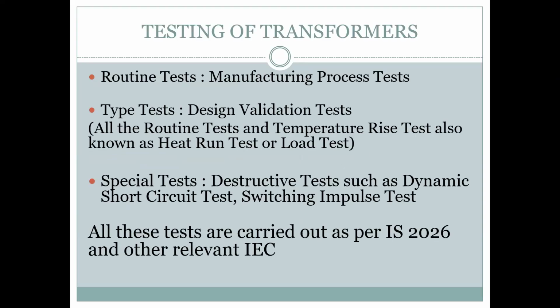These are the routine tests. Basically, every transformer is tested at the factory, and the routine test is a manufacturing test. Whatever design data has been provided, whether it has been tested as per that or not, is compared with the routine test. Type test is a design validation test: whatever design I have done, whether it passes as per that or not. So we go for the routine test plus the temperature rise test, which is also a different test.